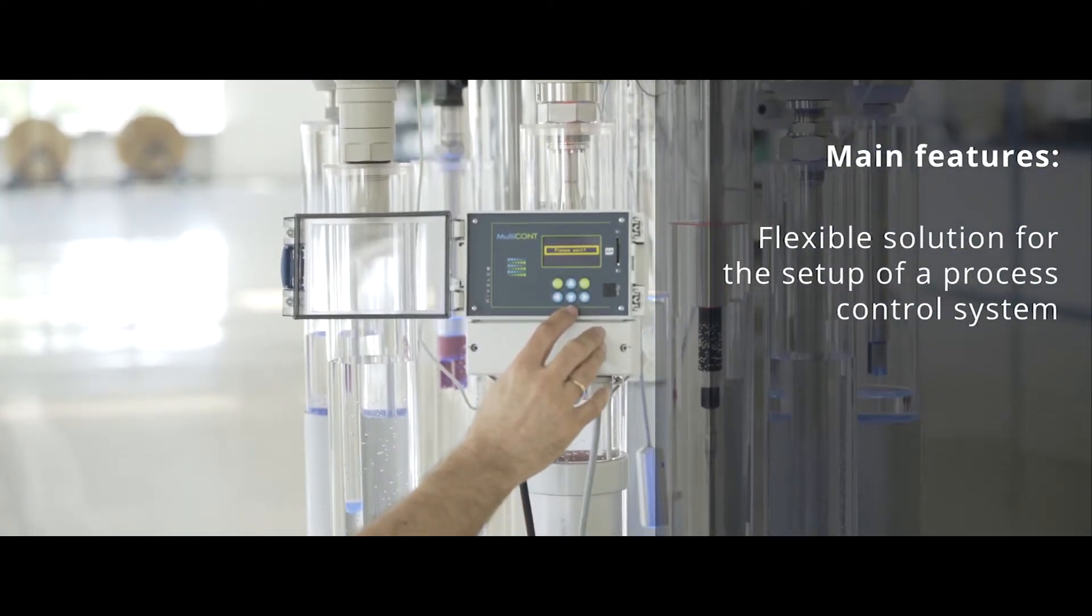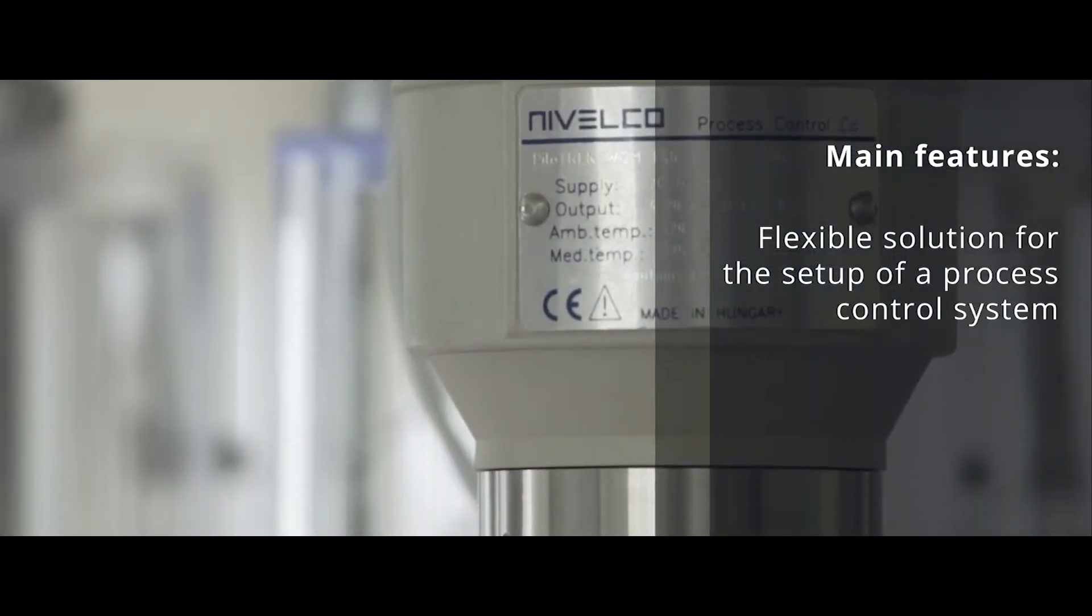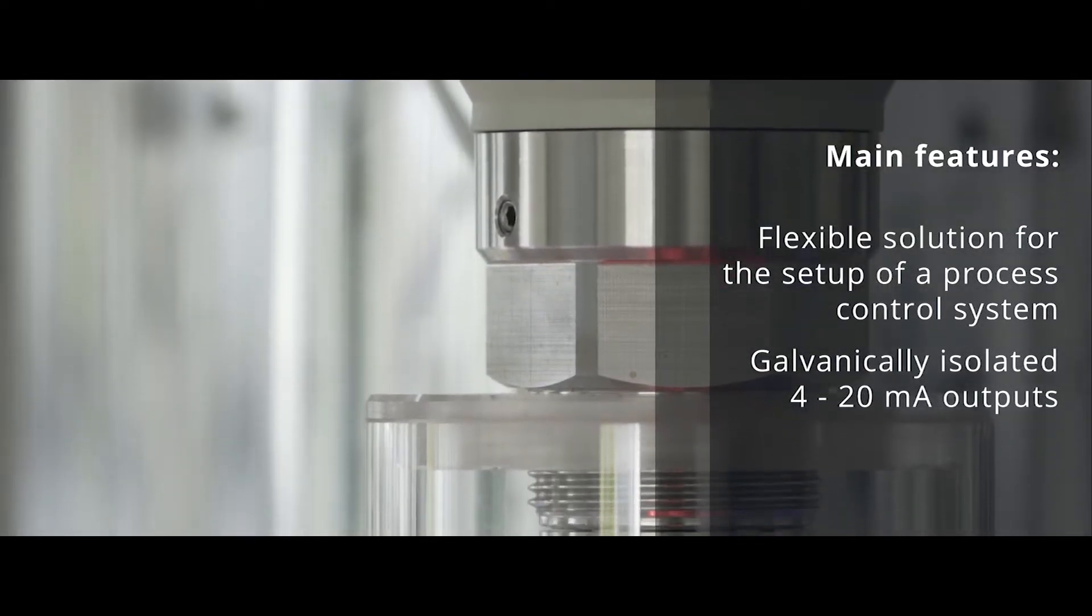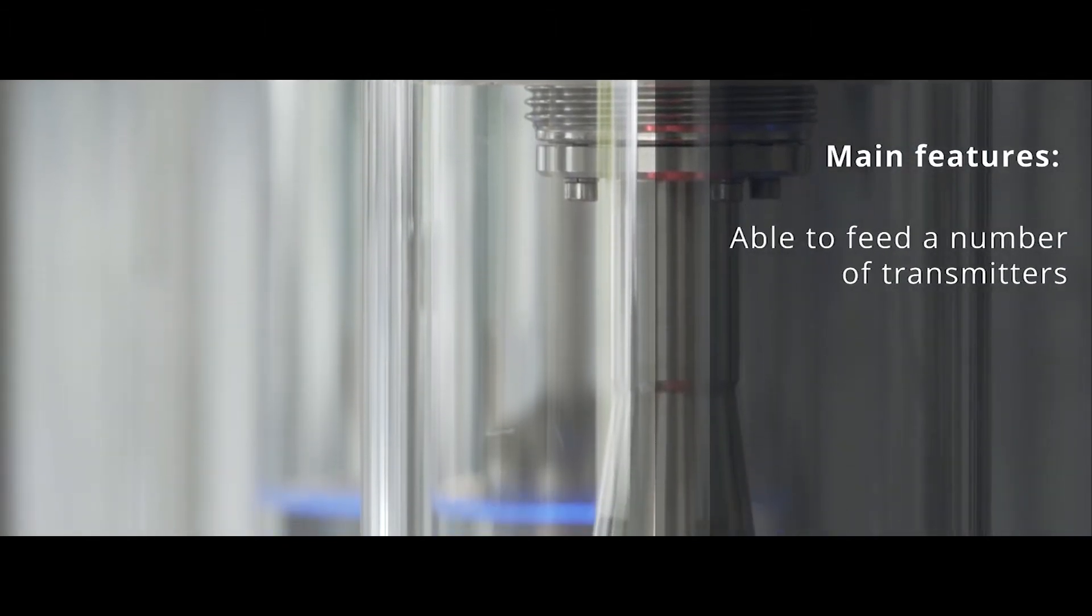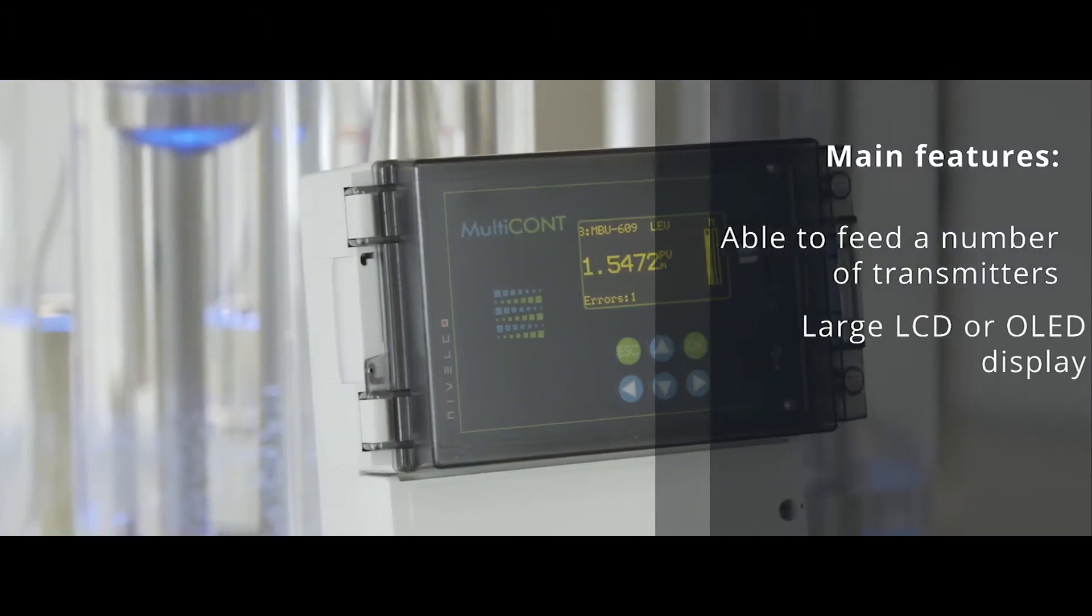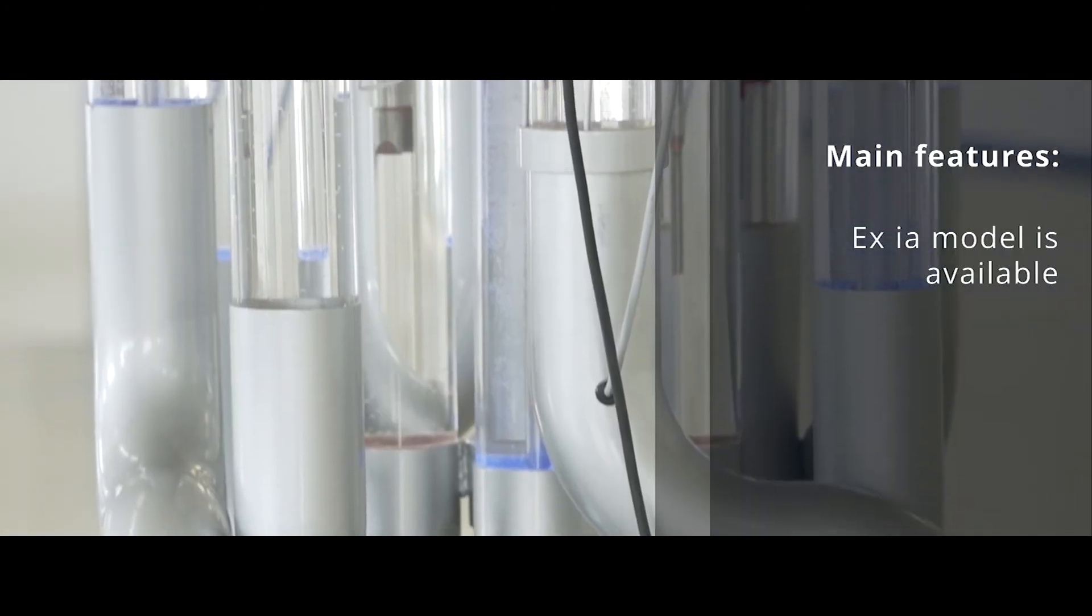The main features of Multicont are the following: flexible solution for commissioning a process control system consisting of Nivelco's HART-based intelligent level, temperature or pressure transmitters. Galvanically isolated 4 to 20 mA outputs assignable for the transmitters. Can feed up to 15 standard or a maximal of 4 ATEX rated transmitters. Highly informative large LCD or OLED display. ATEX model is available. Simple six-button programming. Trend logging into internal memory or external SD memory card.